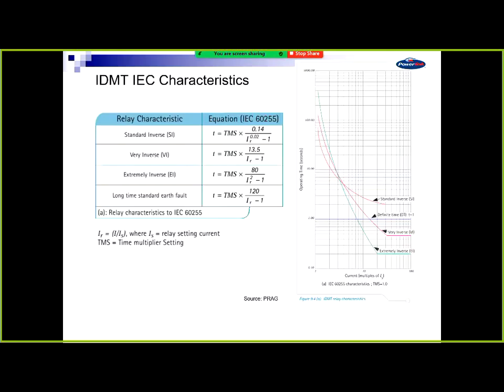They're just the formulas for those three that I've just mentioned there, which are common. The common one being the standard inverse there. You go into a relay manufacturer's manual and you'll see many different curves in there. That actually comes from a book called PRAG, which is a little bit old now, the Protection Relay Application Guide.